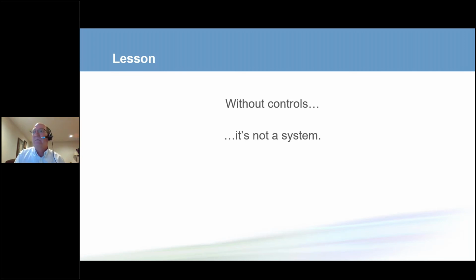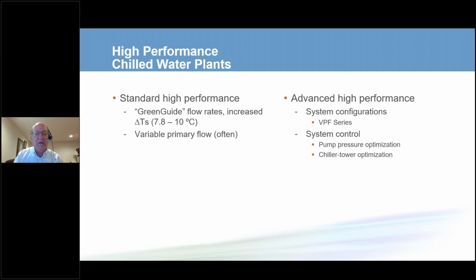So today we covered a number of things. We covered them quickly. There are references available, and I'll answer questions in just a couple minutes. So we talked about first, let's reduce the flow rates. Let's use the ASHRAE GreenGuide recommendations to make our systems more efficient and more cost effective. Let's consider doing the same by using variable primary flow systems. Then, when we look at variable primary flow systems, we can also install them in both new and existing applications. And from a system control, we talked about pump pressure optimization and chiller tower optimization. Now in 45 or 50 minutes, we can't cover all of the questions that you have, but hopefully we'll be able to cover some. So I'd like to leave you with these thoughts.